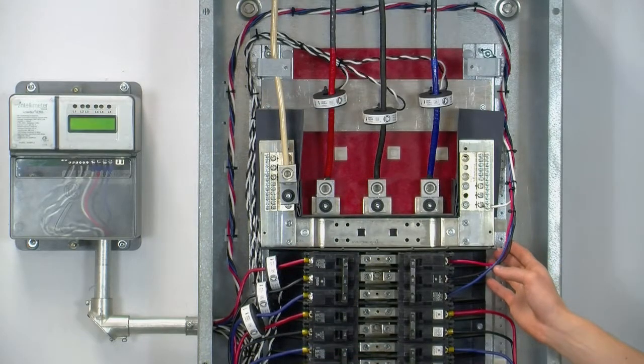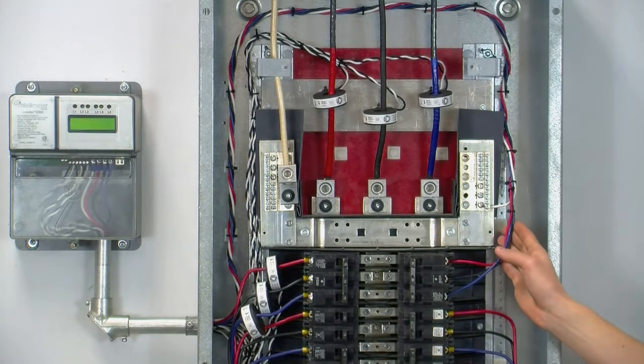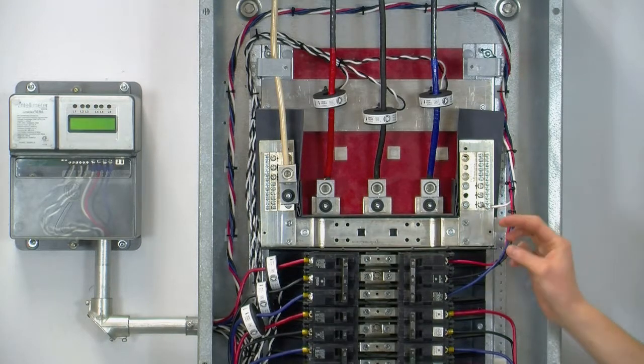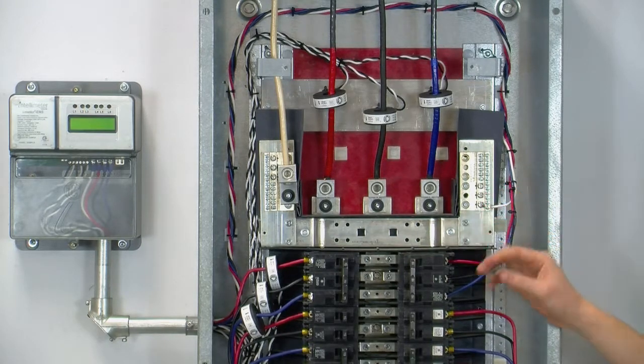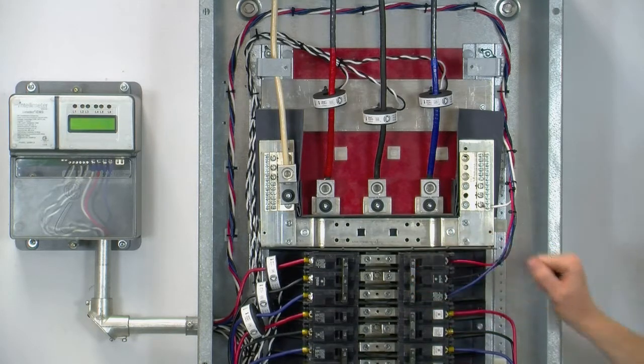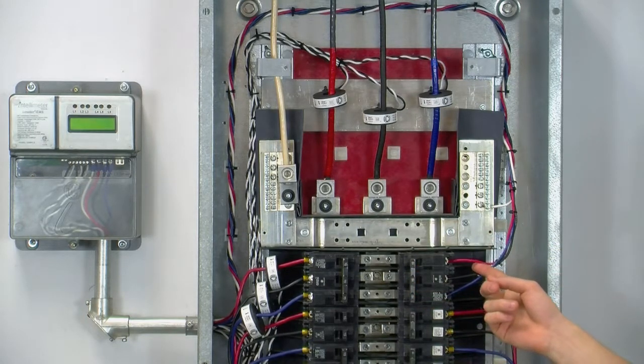Now it's time to install our reference voltage. Now the reference voltage is used to both power the meter up as well as provide the meter with reference to the different voltage phases. Because we're using three-phase metering, a separate three-pole 15-amp breaker will be required for the reference voltage. Make sure to use coloured wires specific to your local electrical code.